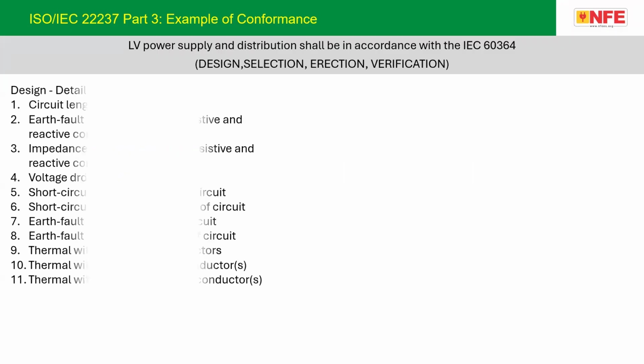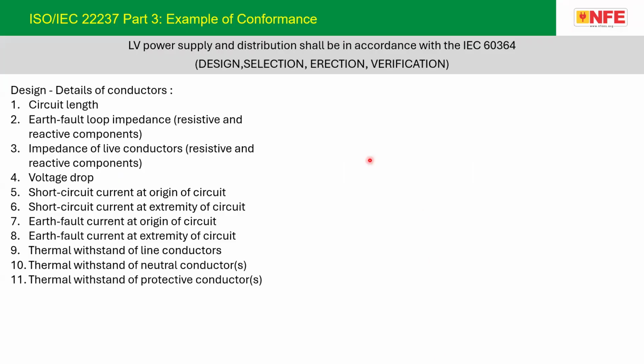Participants, please note that we are not going deep into parts 4, 5, 6 and the other parts of the standard. Now, if we look at part 3, example of conformance, it says that the LV supply and distribution shall be in accordance with IEC 60364. To get compliance to 60364, when we design, the details of conductors, these items in serial number 1 to 10, such as circuit length, fault loop impedance of live conductors, in both cases resistive and reactive components shall be considered, voltage drop, short circuit. All these subjects need to be considered when you select the conductors.